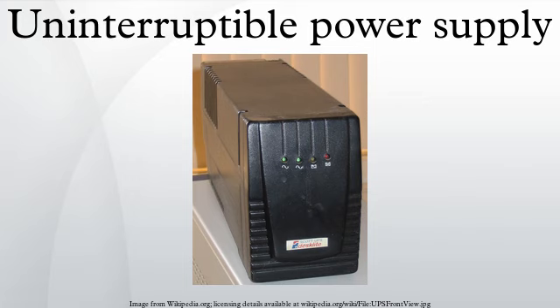Common power problems. The primary role of any UPS is to provide short-term power when the input power source fails. However, most UPS units are also capable in varying degrees of correcting common utility power problems: voltage spike or sustained overvoltage, momentary or sustained reduction in input voltage, noise, defined as a high-frequency transient or oscillation, usually injected into the line by nearby equipment, instability of the mains frequency, and harmonic distortion, defined as a departure from the ideal sinusoidal waveform expected on the line. UPS units are divided into categories based on which of the above problems they address, and some manufacturers categorize their products in accordance with the number of power-related problems they address.